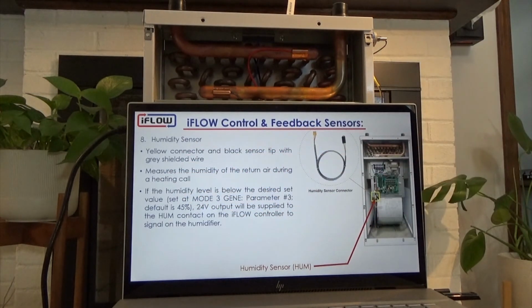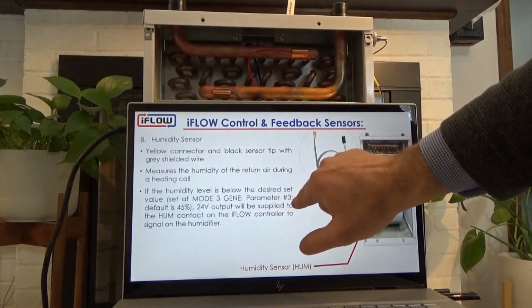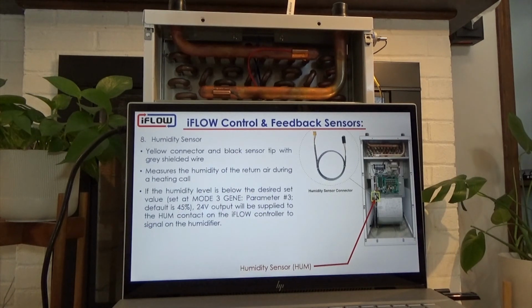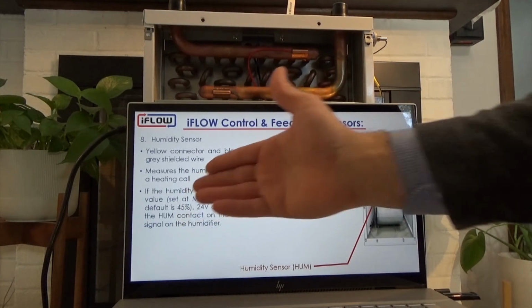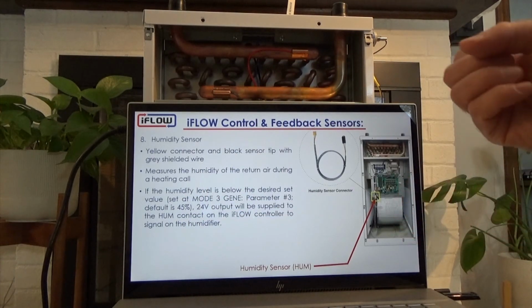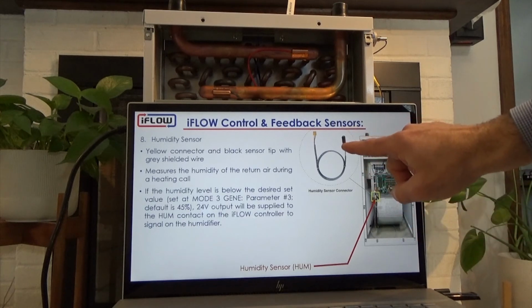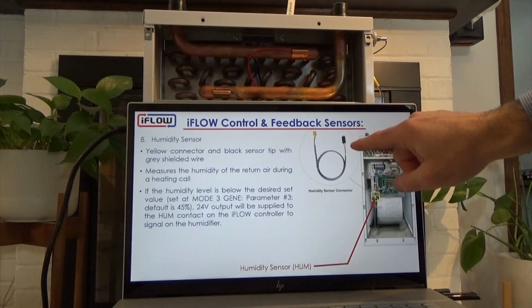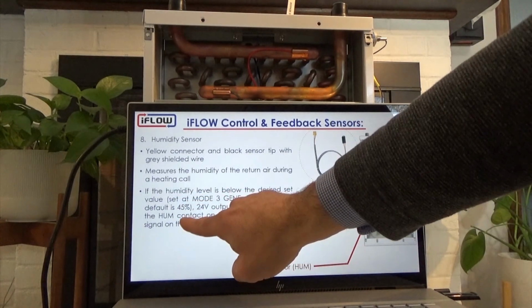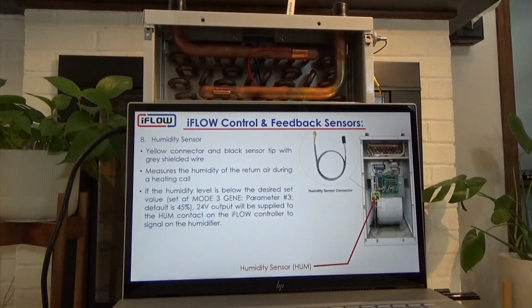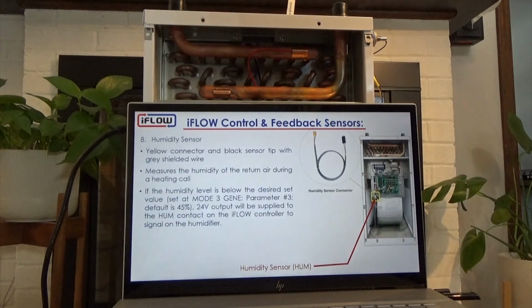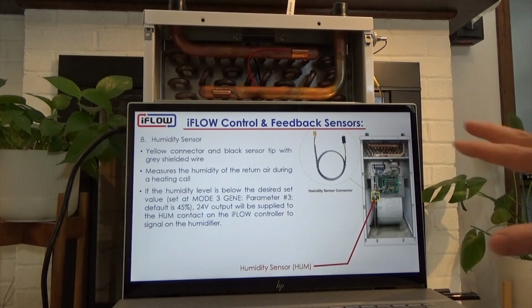On our control, in mode 3, general parameters number 3, we can actually set the humidity level that you want. So if you want 45%, that is our default, then when there's a heating call, the return air comes in, and the sensor will look to see what the humidity level is. If it is below your set value, then it's going to send 24 volts out to the humidifier contact. That's on the left, that's one of our outputs here, and it's going to call on your humidifier. So that's the humidity sensor, again, all built into the iFLOW.